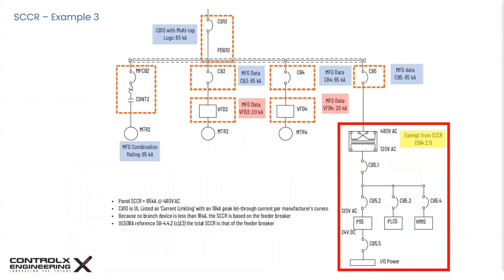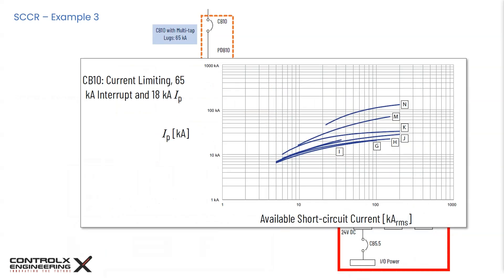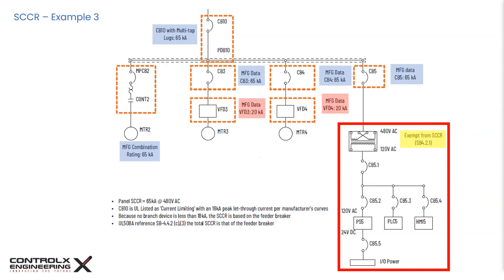In the third example, CB10 is UL listed as current limiting with an 18 kA peak let-through current per manufacturer-provided curves. The let-through current is the maximum instantaneous or peak current that passes through a protective device. Since all downstream devices have ratings exceeding the 18 kA peak let-through current, the overall SCCR is based on the feeder breaker. Therefore, per paragraph SB 4.4.2, the panel SCCR is 65 kA at 480V.